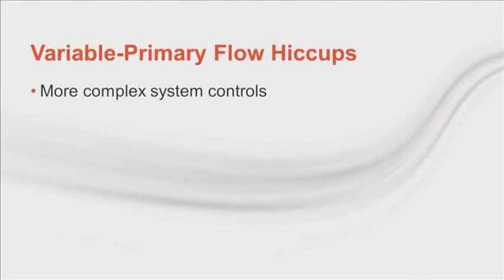As discussed in the 2008 program on small chilled water plants, staging on a second chiller is a difficult transition. The flow rate through the operating chiller is cut in half, and the chiller has to unload fast enough to avoid the low evaporator refrigerant cutout. Simply stated, some things have to happen quickly and some things slowly. The new circuit has to open slowly, and the chiller has to unload quickly. If they don't, the chiller will have a nuisance trip. Now, this stops being a nuisance pretty quickly and may become a deal breaker.